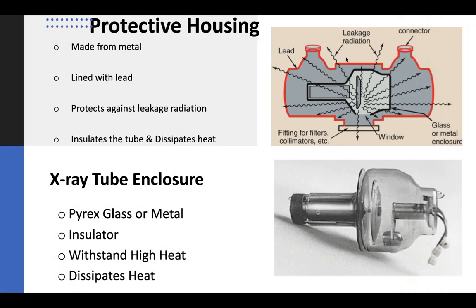The protective housing is one of the external components of the X-ray tube. The protective housing is lined with lead and made from metal. The lead-lined housing is to provide an additional shield against leakage radiation as well as protection from electric shock. X-rays are emitted isotropically, meaning they travel in all directions. This helps to prevent excess radiation from leaking into the examination room.